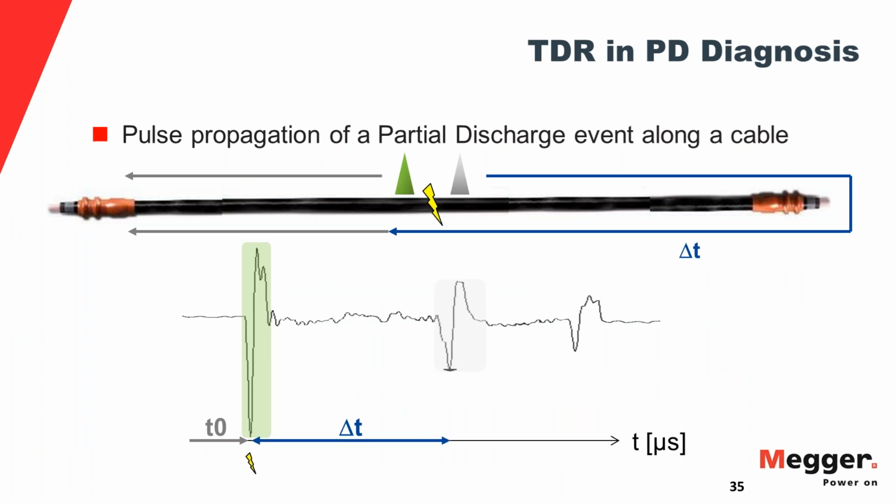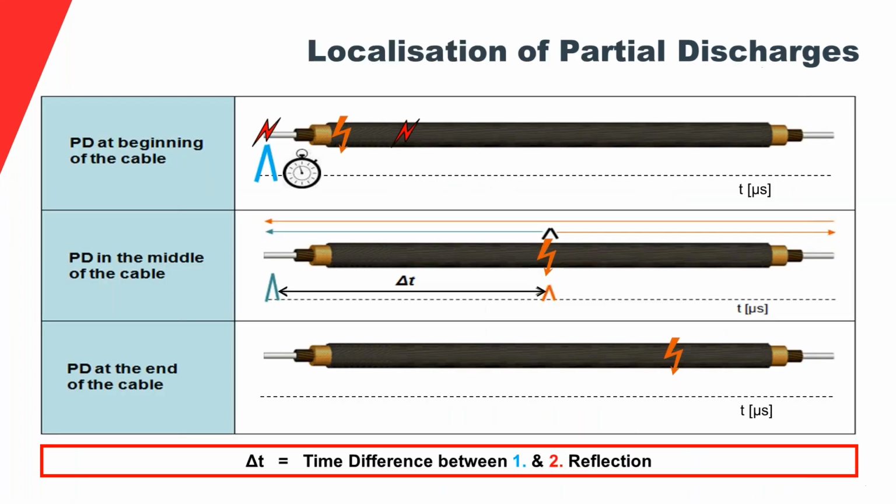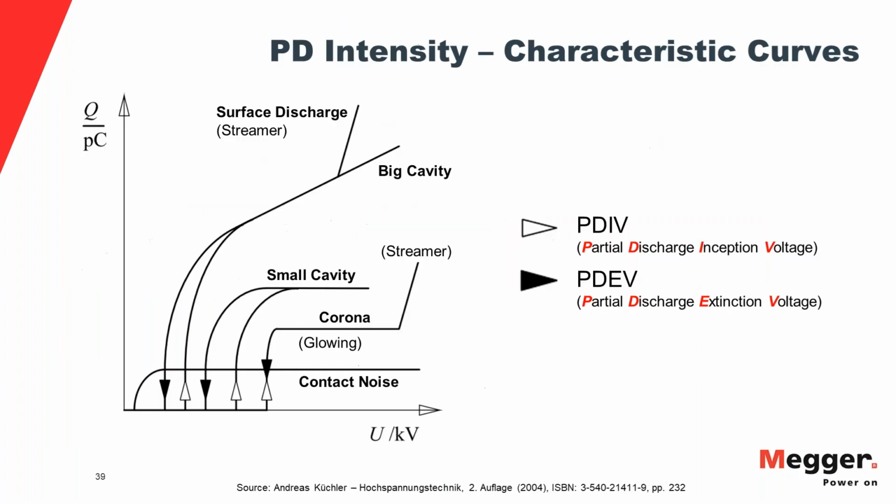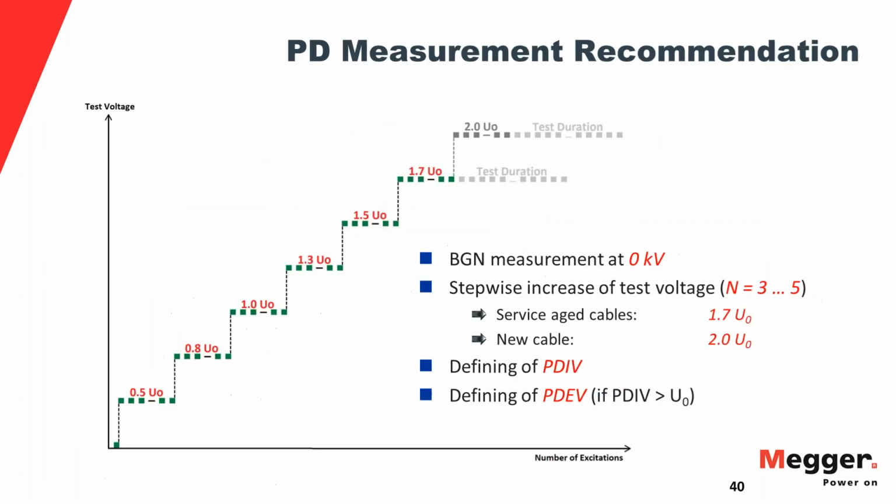And then you save that trace, and the software will use this as its gold standard for the measurement to discriminate against. So any pulse that runs into it will be judged against that calibration pulse that you recorded earlier on. And then you do a background noise measurement.